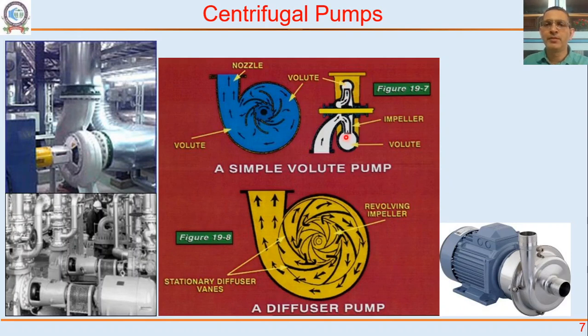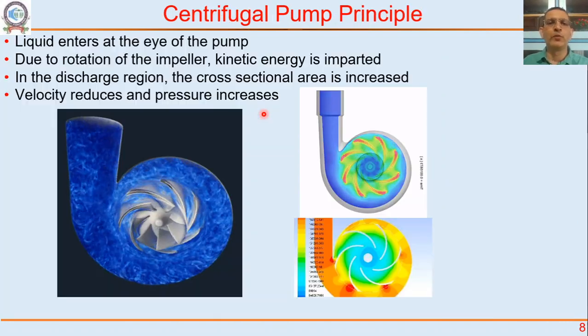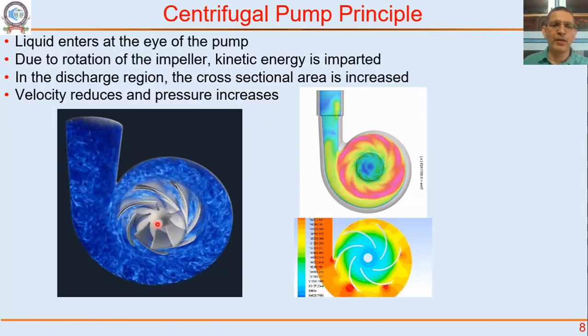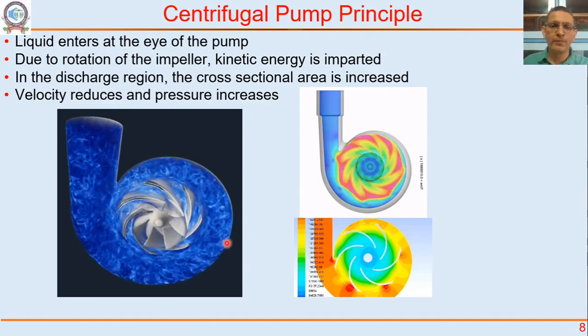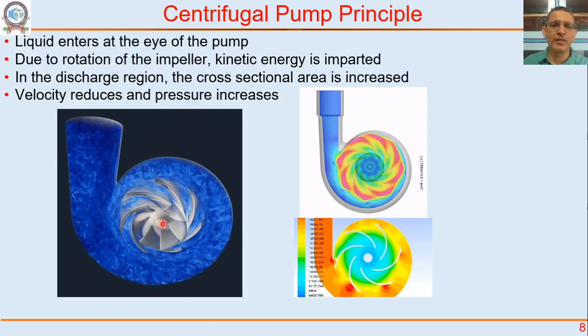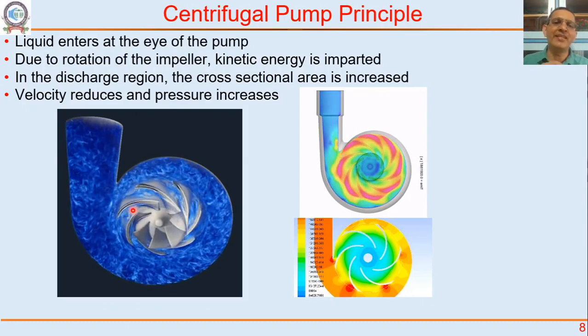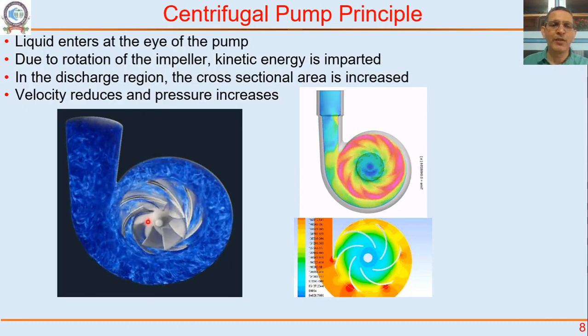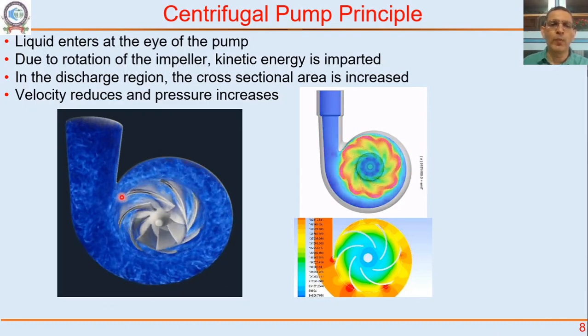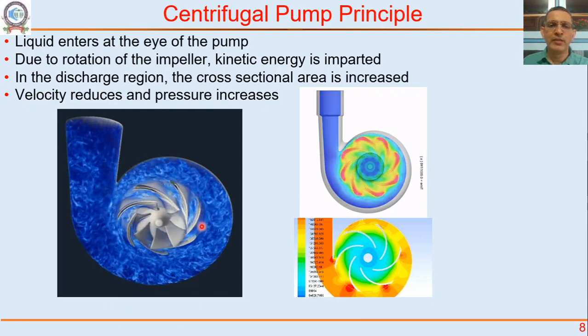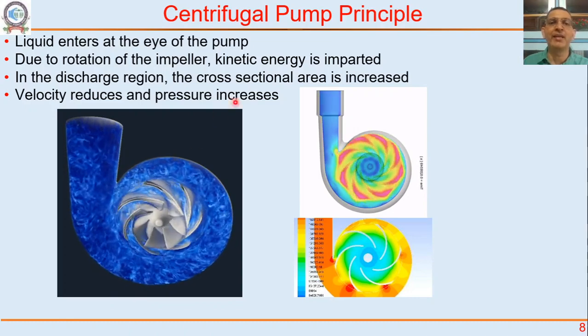The impeller is rotating. Liquid is coming from the eye of the impeller. The rotation of the impeller increases the tangential velocity of the fluid. Tangential velocity here at the center is very small, but at the edge it is 2πRn — that is the tangential velocity imparted. So this tangential velocity is high at the edge. The impeller is imparting kinetic energy to the liquid. What is plotted is contours of velocity — red regions are high velocity, blue regions are low velocity. Velocity is high at the edge of the impeller.